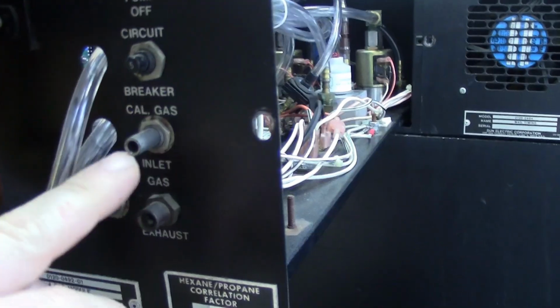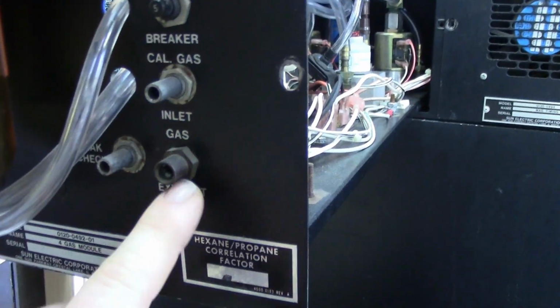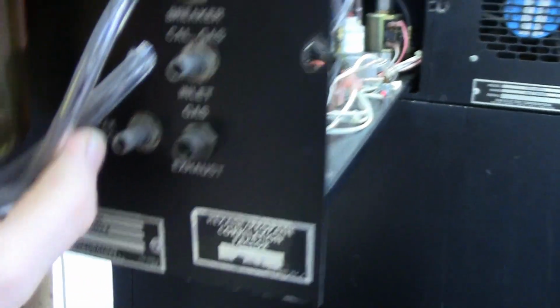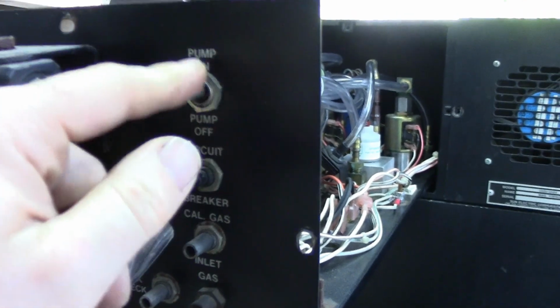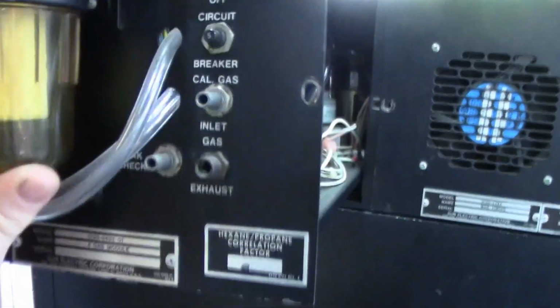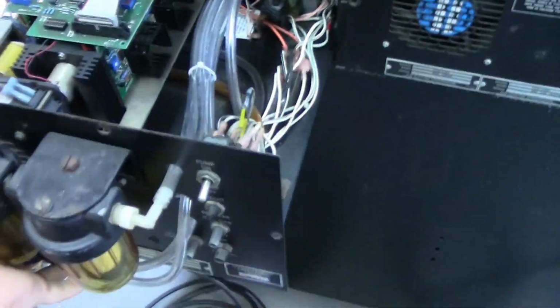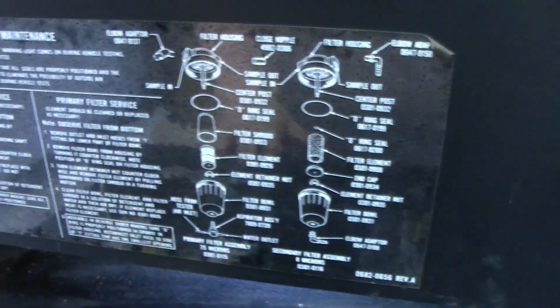These are the various solenoids and electronic valves which control the routing of all the hoses here. Because not only will it be drawing air in, there's also additional ports here for a calibration gas, your exhaust port down there, and a leak check, which just makes sure that under normal conditions this isn't leaking and diluting the mixture that's going into it. This also has its own separate switch. And that would just kind of go back in there, but it's getting stuck, whatever, we're going to deal with that. And there is a nice little diagram here on how each filter goes together.